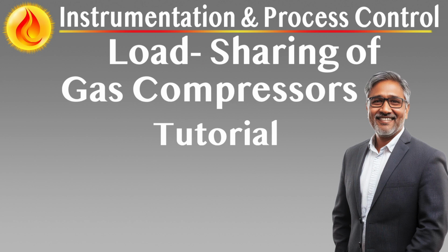Instrumentation functionality, primary capacity control. The station pressure controller calculates flow or pressure deviation and issues a shared command, CRSC. Depending on system state, if non-recycling, the load-sharing controller acts on CRSC to increase throughput. If recycling, the anti-surge controller adjusts its output using CRSC to reduce net flow while preventing surge.